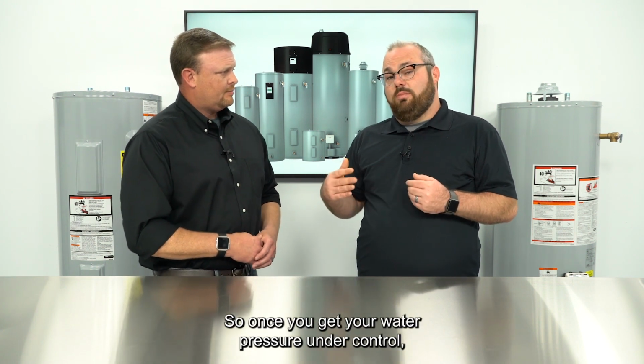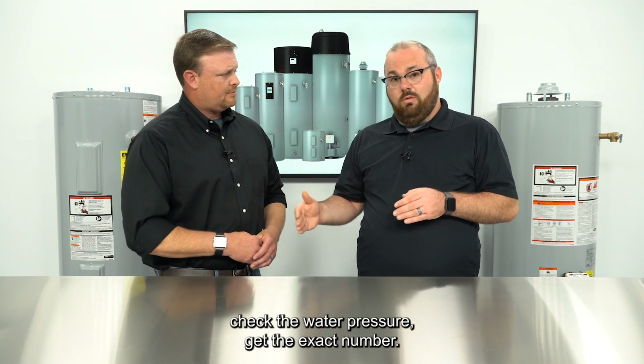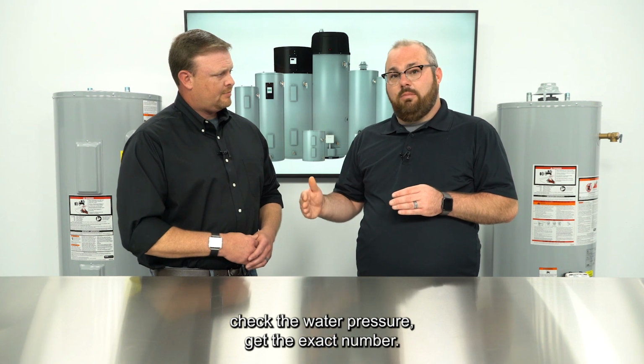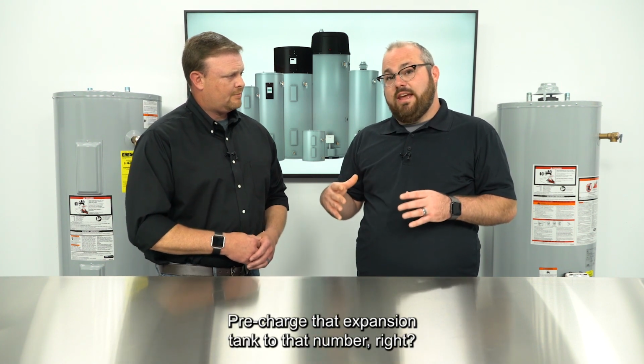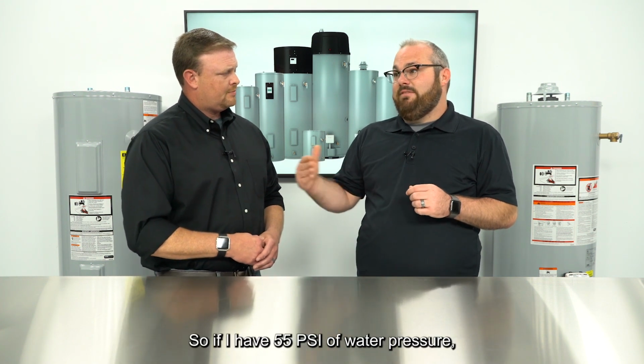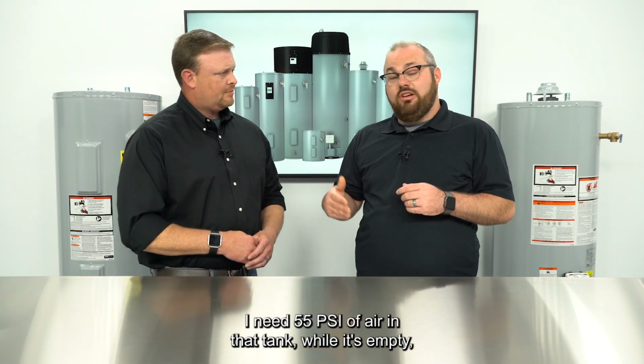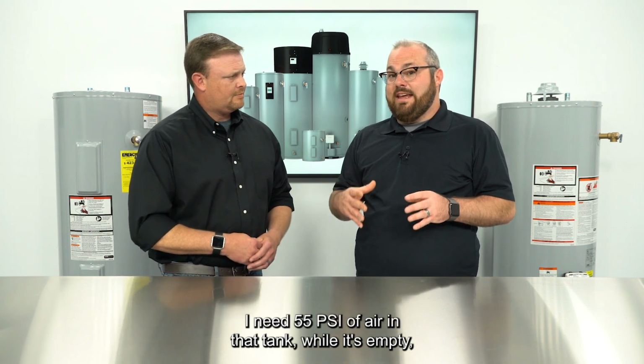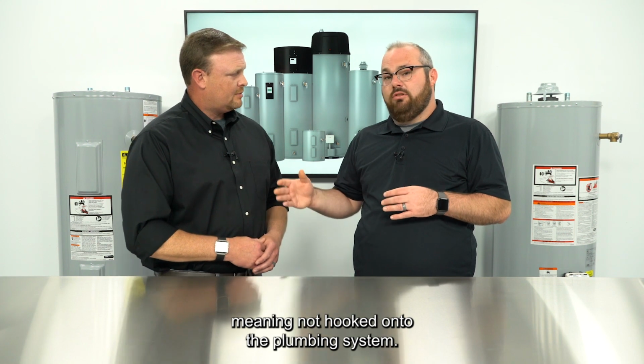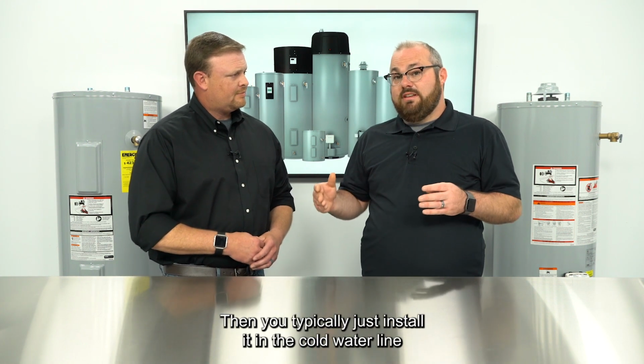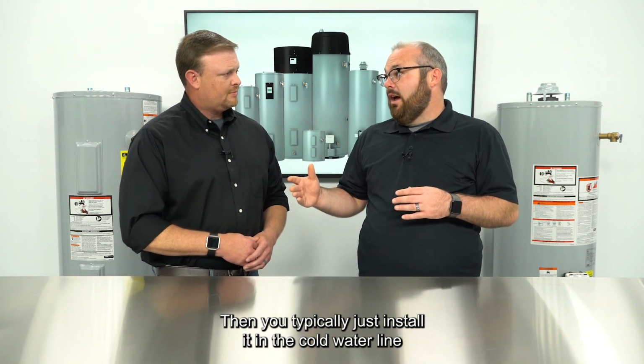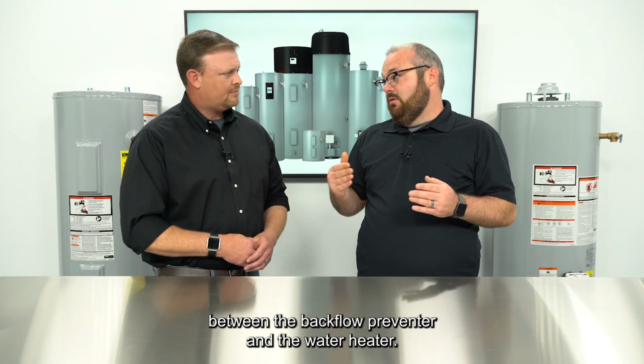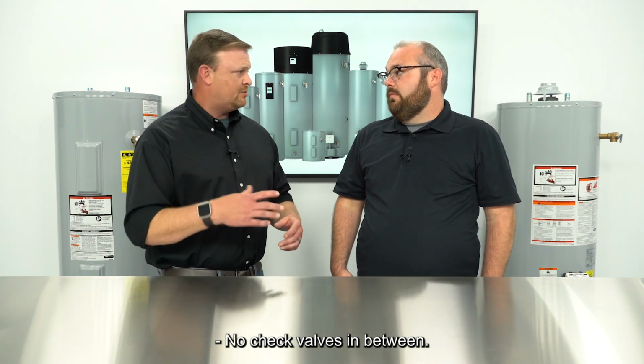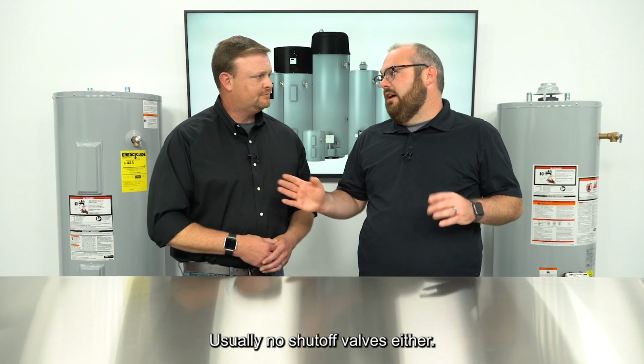Once you get your water pressure under control, check the water pressure, get the exact number, and pre-charge that expansion tank to that number. So if I have 55 psi of water pressure, you need 55 psi of air in that tank while it's empty, meaning not hooked onto the plumbing system. Then you typically just install it in the cold water line between the backflow preventer and the water heater. So no check valves in between either? Correct. Usually no shut-off valves either.